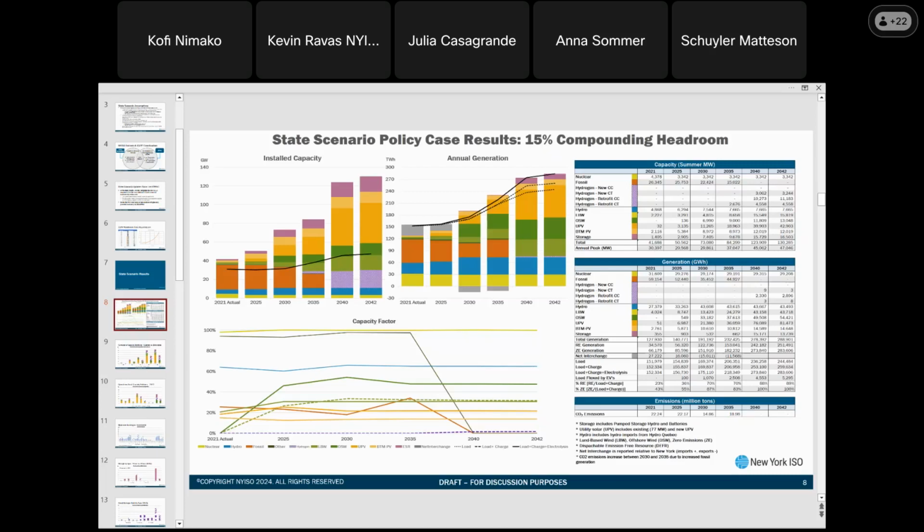In terms of the energy dispatch, we have a lot of energy on the system, and it's typically better in these really high renewable systems to let as much of that solar and wind get delivered directly to load as possible without having to go through that energy-losing translation of going through a storage device. And so there's a lot of shoulder days where the storage will operate very, very minimally, and that reduces the amount of energy that you can really get out of the storage.